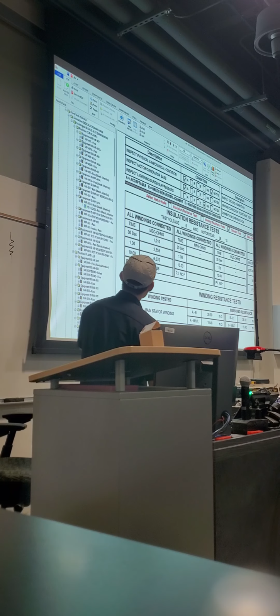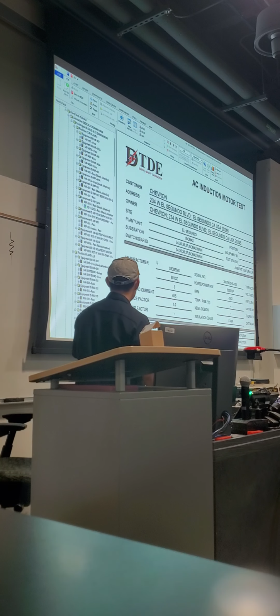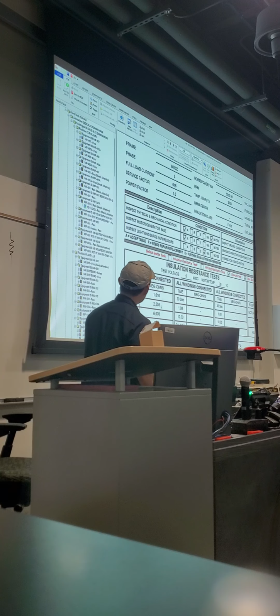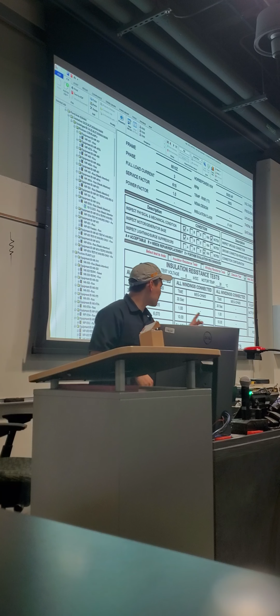So in this case, we had 1,010, or in this case it would have appeared as 1.01 gigohms on our instrument, and then we would have converted it as it called for. It ended up at 6 gigs, which we know is a passing value, right? And we calculate the 2.38 PI. If we look at that chart on Megger, a PI above 2, like I said, is fantastic. So this one was good to go.